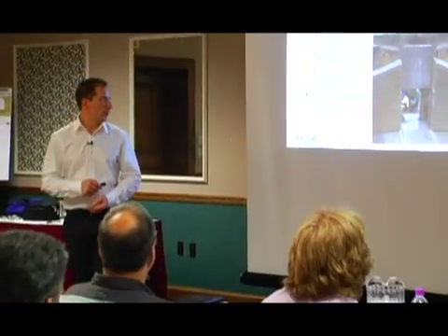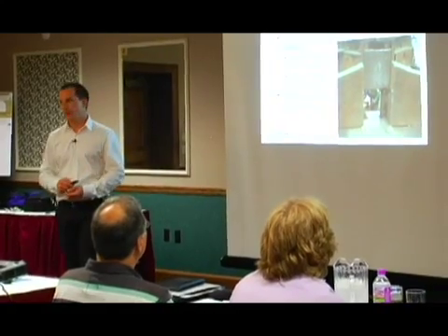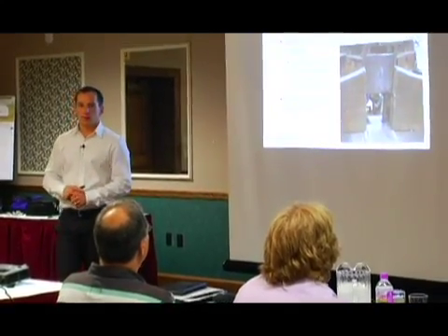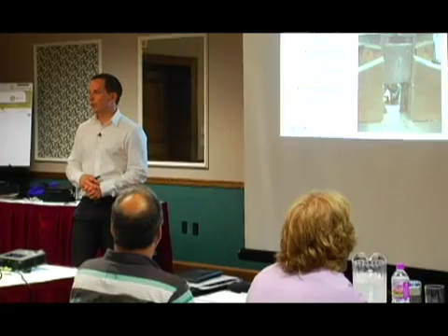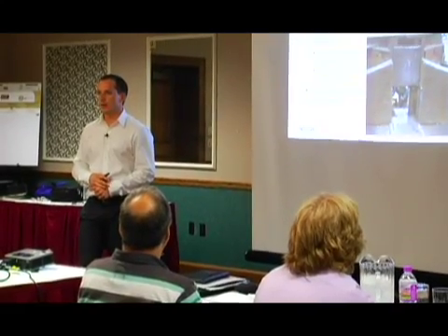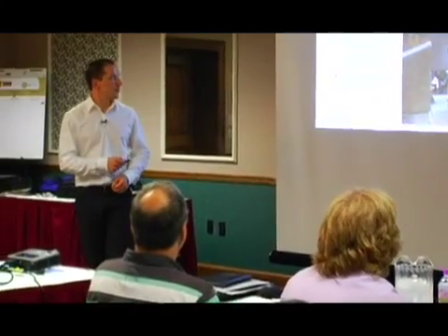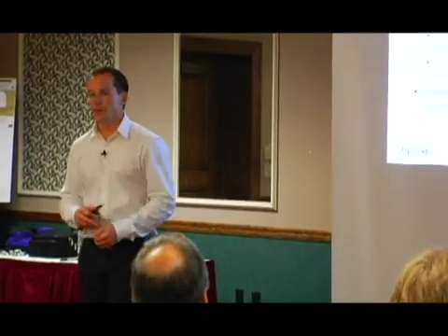What's the disadvantage of wood, even though it ideally can support up to 5 ton? Ages, right? People run over it with forklifts, dump grease on it, it gets splits. And then the theoretical maximum goes way down. I wouldn't trust it to over 500 pounds, let alone 10,000. So instead, always use a specially designed block if it's available. Until then, maybe use 2 wood blocks if it's a piece of machinery you're unsure of.